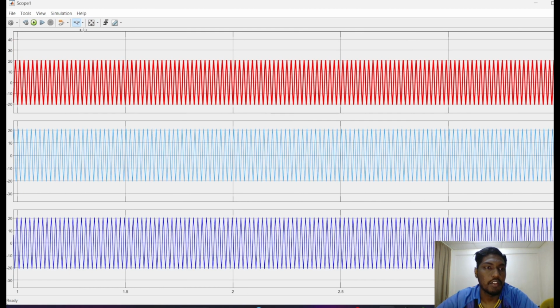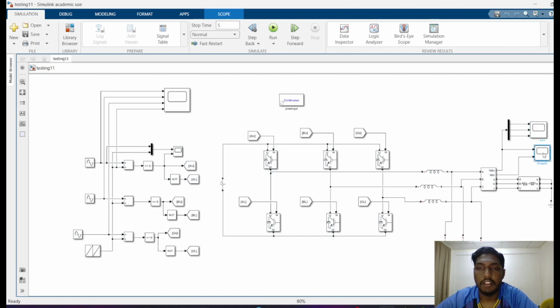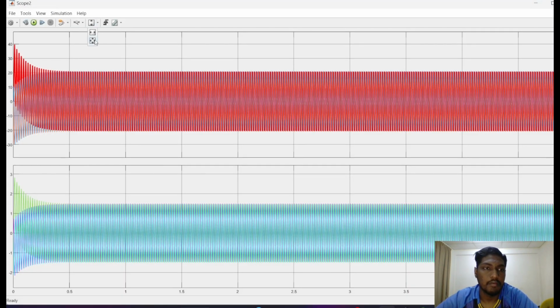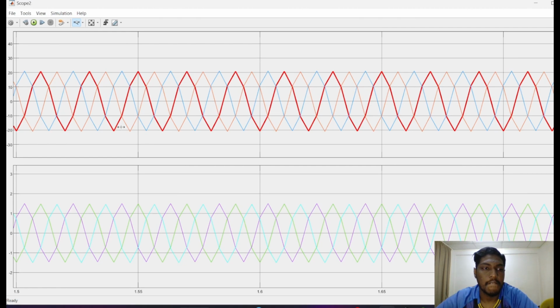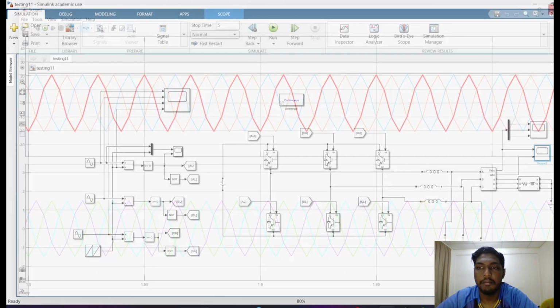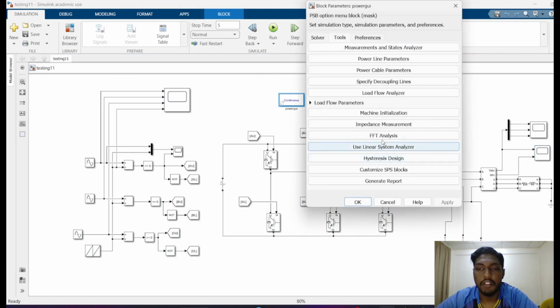and this is for the voltage waveform, and we go to the current, and this is the waveform for the current, as we see. This one is voltage and this one is current. The current is approximately 1.4 amp. And next one, we go to the main thing, that is THD, total harmonic distortion.